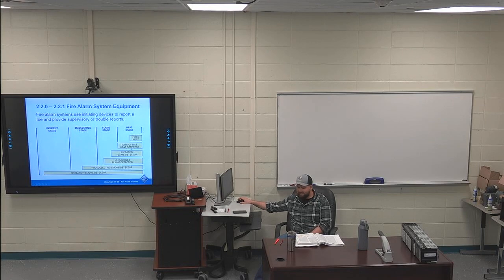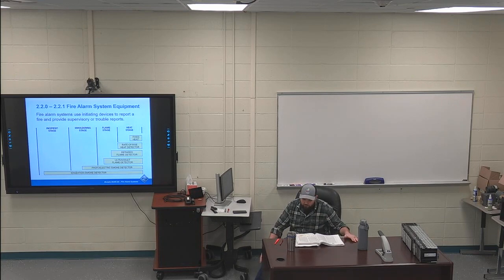rate of rise heat detector. So you can have a heat detector that actually senses the temperature in the room or as it's rising. Out to the side of that, I wrote rate of rise detector can only be used in the heat stage of a fire. So if you're using a rate of rise detector, you can only use that for the heat stage. It does not work in the flame stage, smoldering stage, or incipient stage.